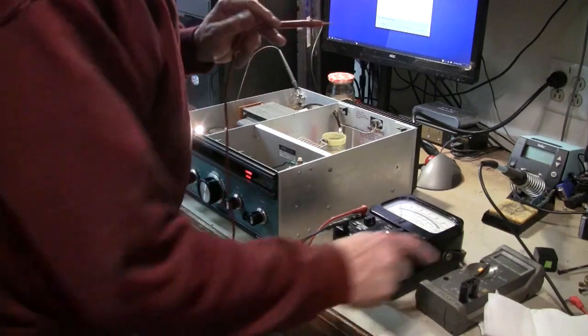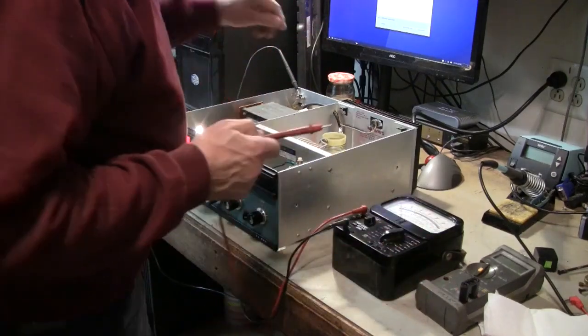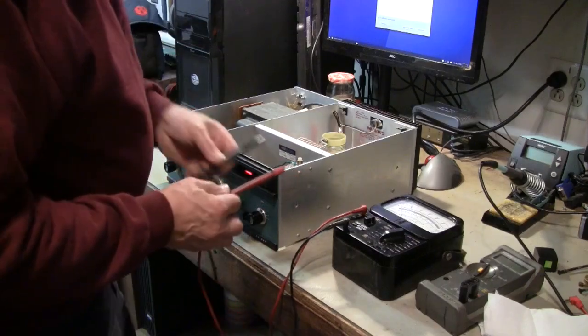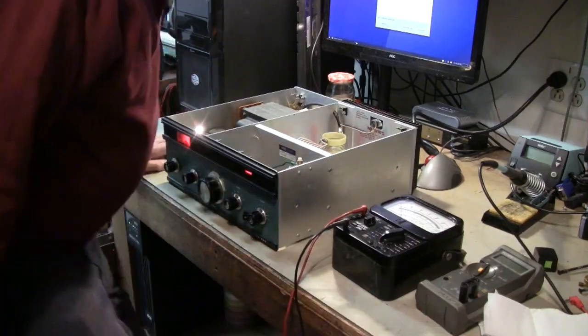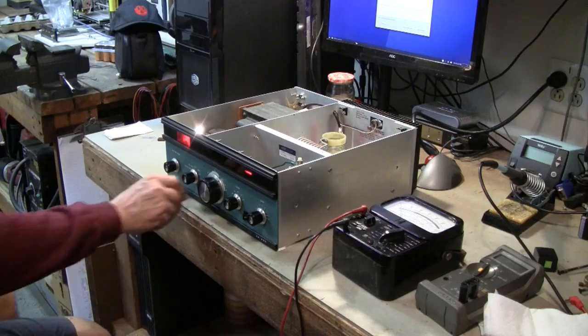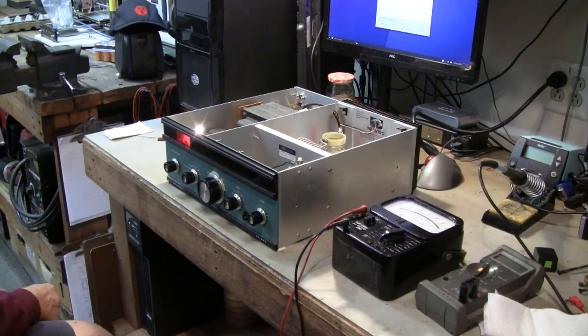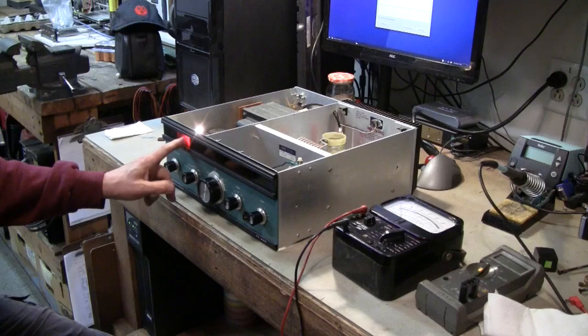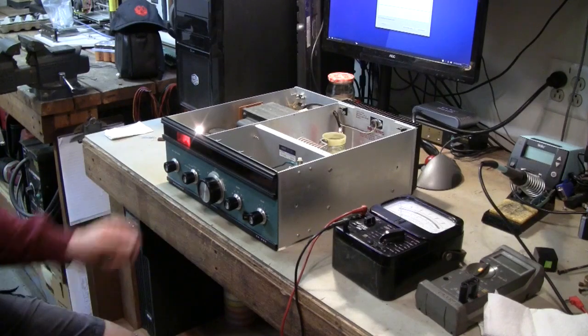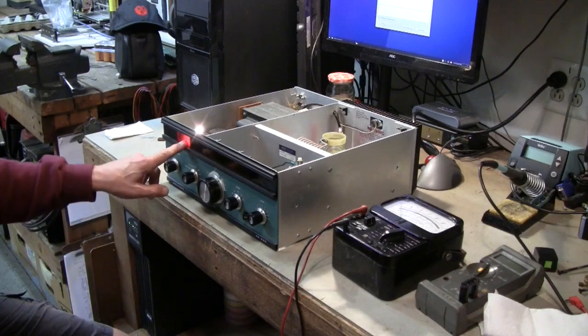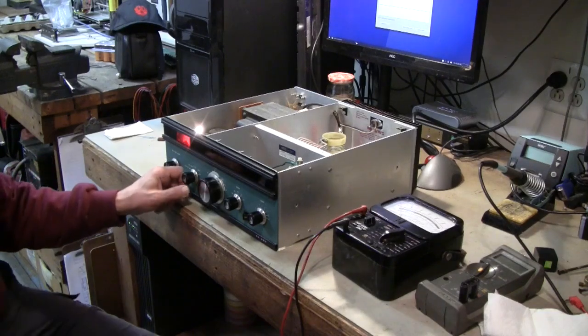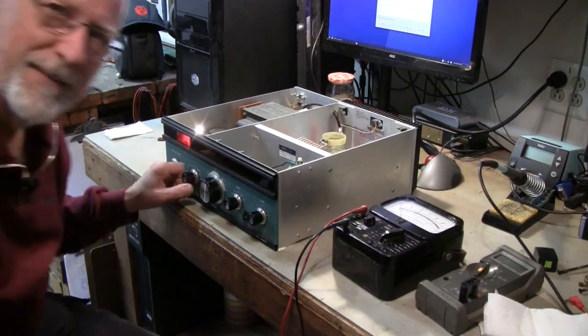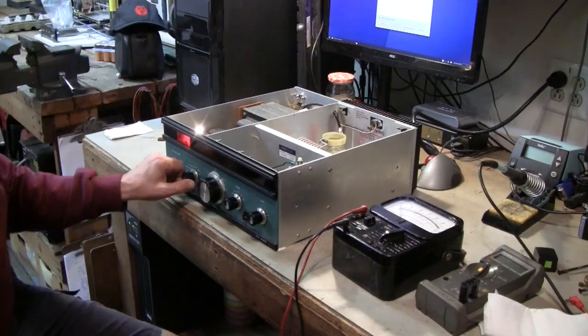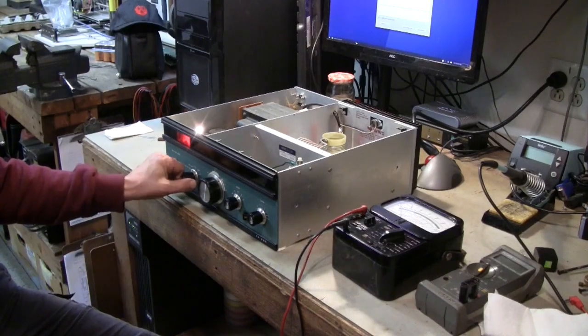The digital multimeter reads 2185 when I check it with that. And the meter is showing 2,200 volts. So I might want to calibrate this high voltage range on the front panel meter just a little bit, because, you know, that's just the way I am. I like everything to read exactly perfect.